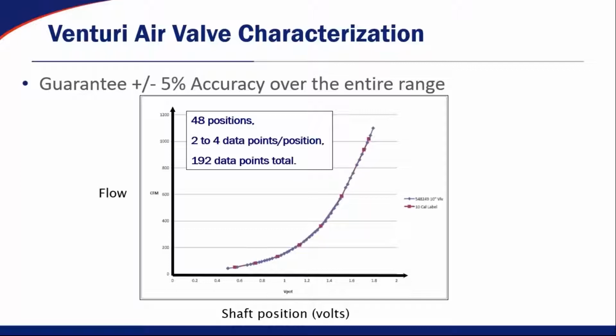The reason we do that is we know when our valves get installed in a building, they're not going to be running at one differential pressure all the time. We know that they're going to be running at various different differential pressures. So at every single flow position across the entire flow range of the valve, we're testing at multiple pressures, and then we're averaging those points to get the accuracy across that full flow range of the valve.